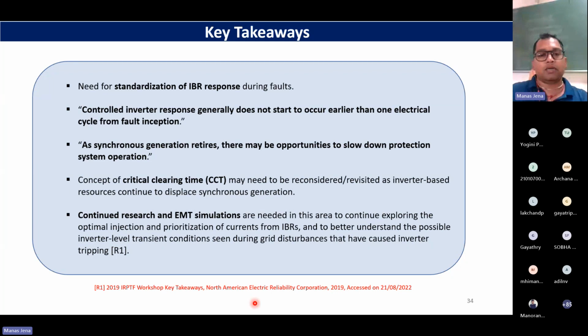you can refer to this very interesting document, the workshop by the North American Electric Reliability Corporation. There were many vendors, protection vendors, inverter manufacturers, OEMs. Many people came and they had a discussion about this aspect. One of the points was that inverter response generally does not start to occur earlier than one cycle, but from the protection perspective, we usually detect within one cycle. So there is a dilemma, right? As synchronous generators retire, there may be opportunities to slow down the protection system operation.